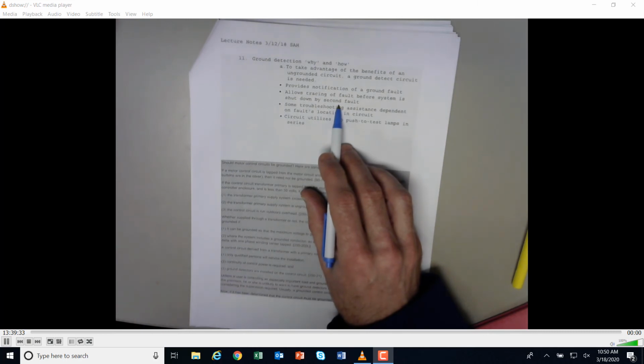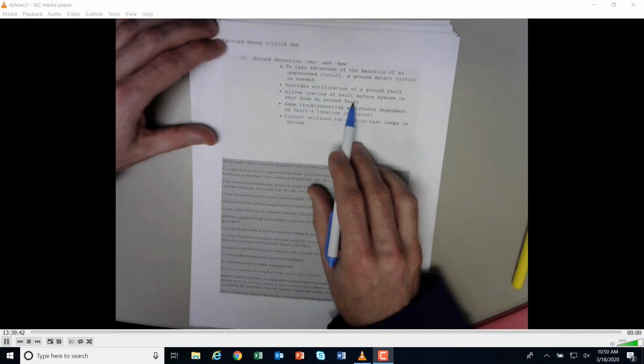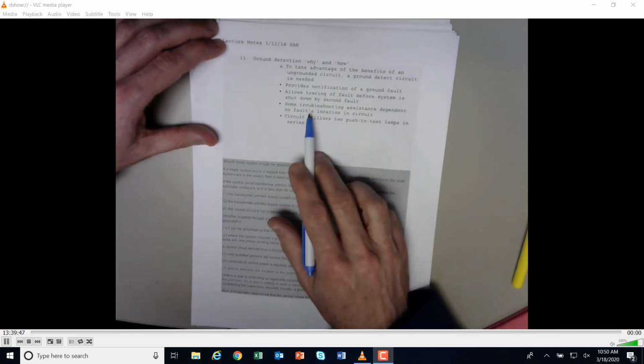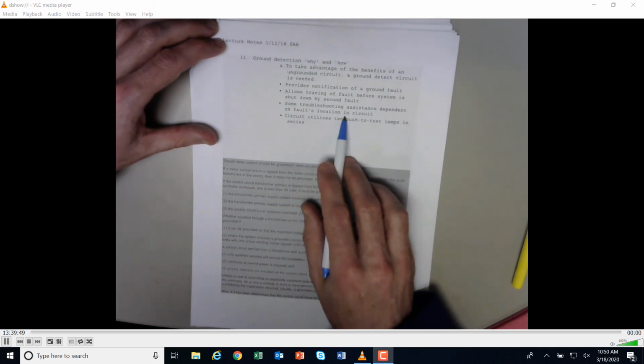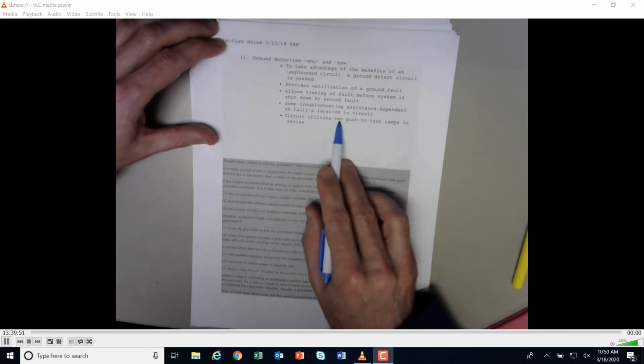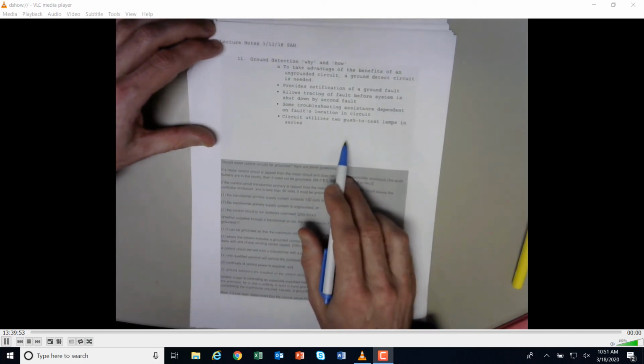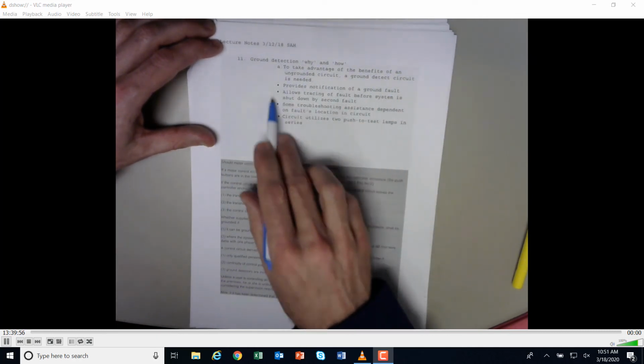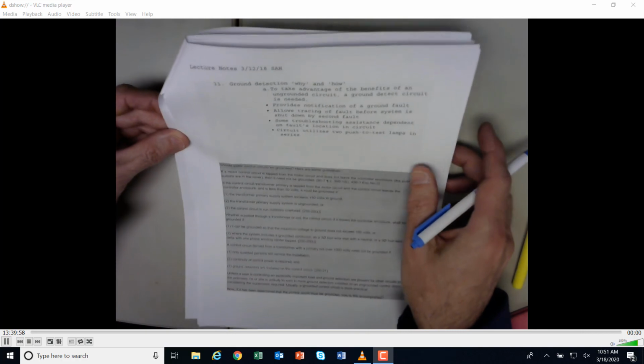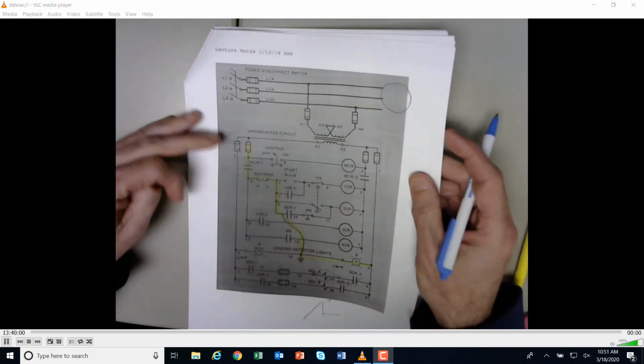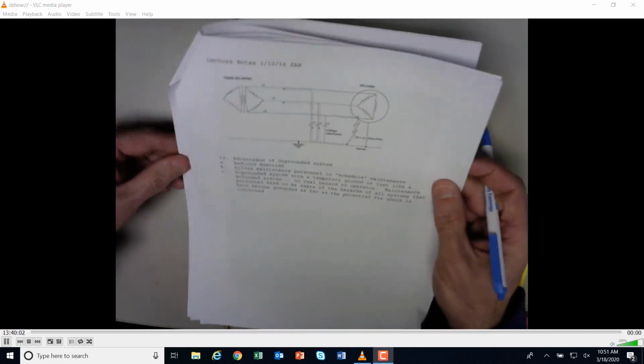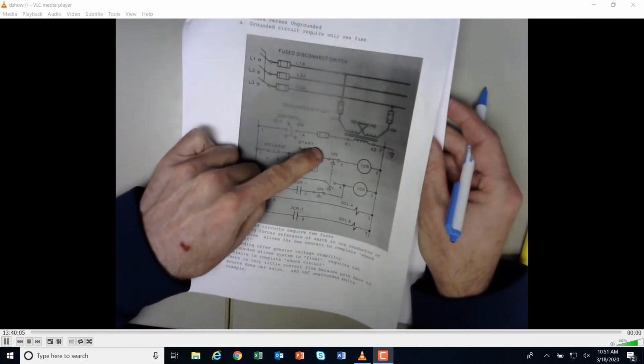And so that's where you could go through the operation of each rung and find out which rung is causing the light status to indicate where it's at. It provides some troubleshooting assistance depending on the fault's location, and it uses those two push-to-test lamps in series. So that is a quick summary of how that ground fault circuit is going to work here.